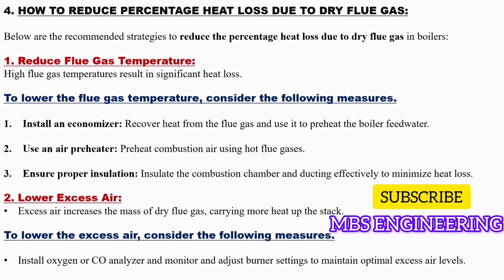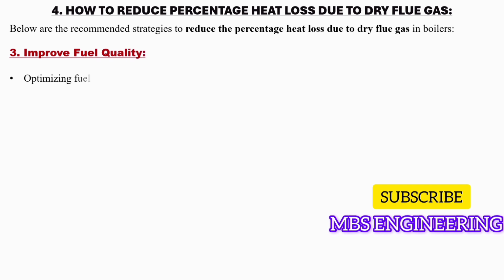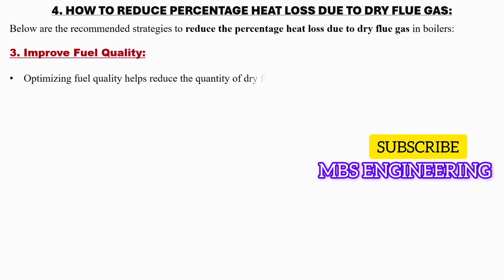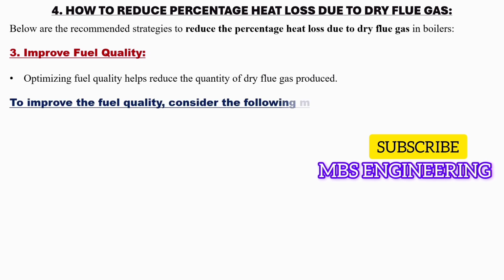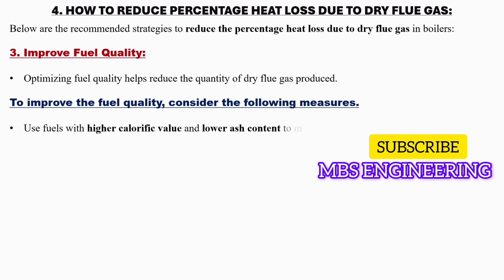Next, we will learn and understand how to reduce percentage heat loss due to dry flue gas in a boiler system. Below are the recommended strategies to reduce the percentage heat loss due to dry flue gas in boilers. The third recommendation is improve fuel quality. Optimizing fuel quality helps reduce the quantity of dry flue gas produced. To improve the fuel quality, consider the following measures. Use fuels with higher calorific value and lower ash content to minimize dry flue gas mass. Maintain the appropriate fuel-air ratio for efficient combustion.